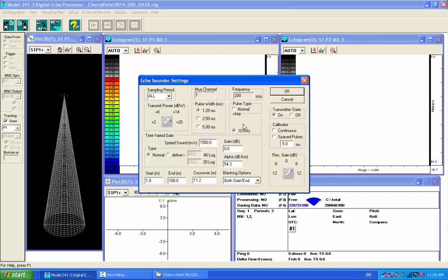I told Pat it was good to ground the generator. Right, we grounded it differently and that helped. But I think normally we would ground to the hull on the aluminum vessel, and as I recall, Pat ran a ground lug right from the generator to the back of the echo sounder. Right. Yeah, which then basically gave a noise path into it without a ground, because there wasn't a ground. It was just whatever was feeding from the generator, right? We had all those issues, remember, too. Yeah, we had some. We just did all sorts of stuff.